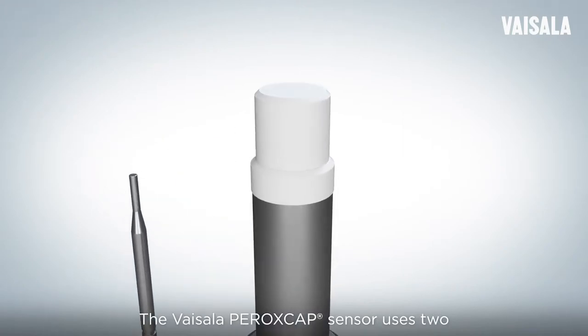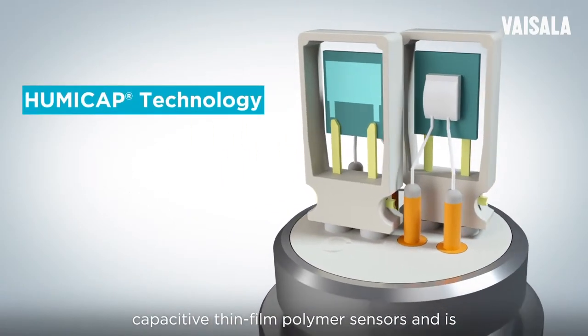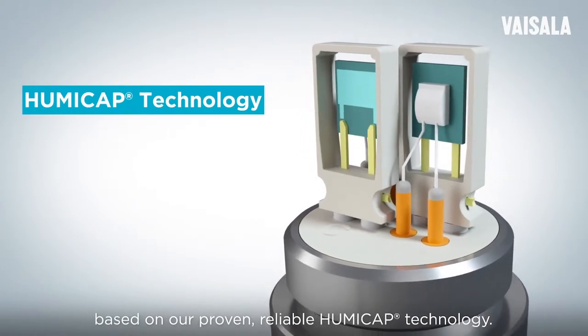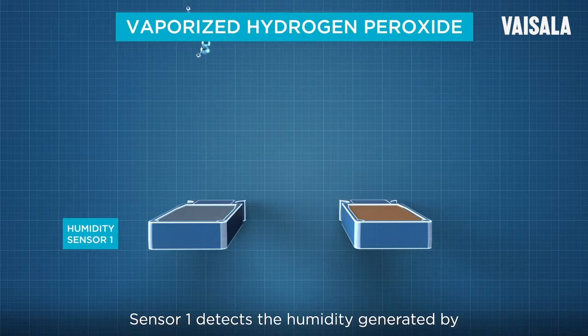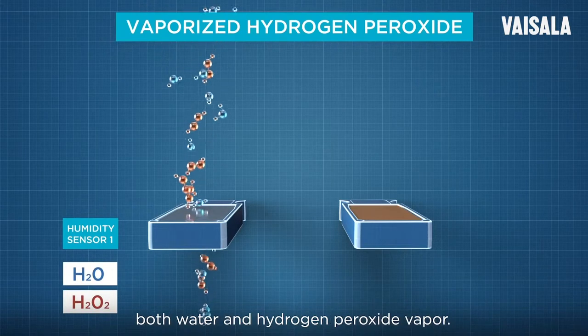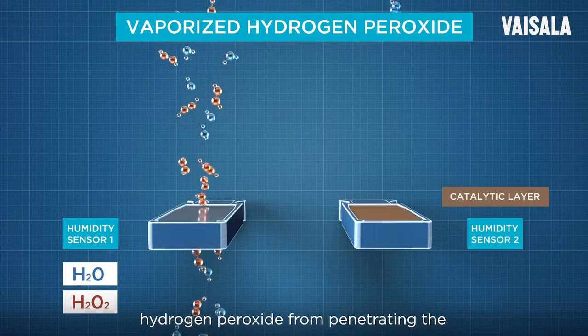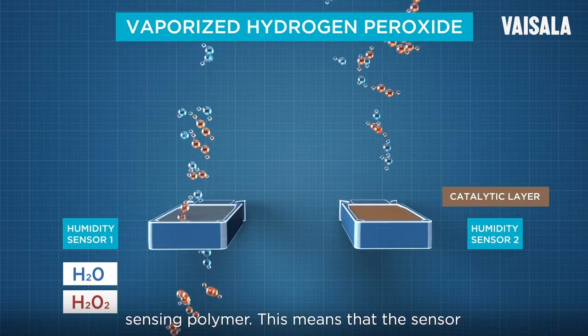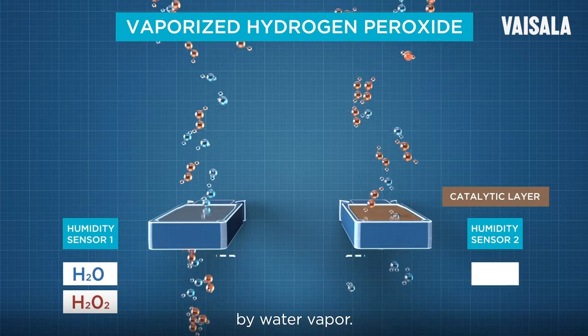The Vaisala Peroxcap sensor uses two capacitive thin-film polymer sensors and is based on our proven reliable HumiCap technology. Sensor 1 detects the humidity generated by both water and hydrogen peroxide vapor. The catalytic layer on top of Sensor 2 prevents hydrogen peroxide from penetrating the sensing polymer, meaning that sensor only measures the humidity generated by water vapor.